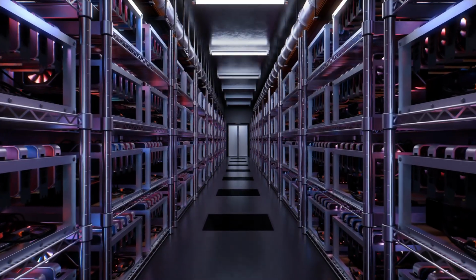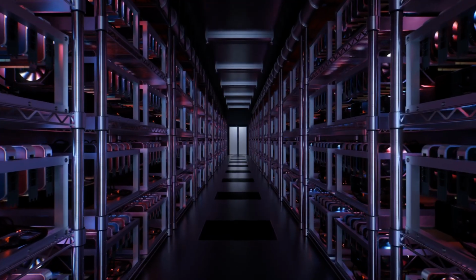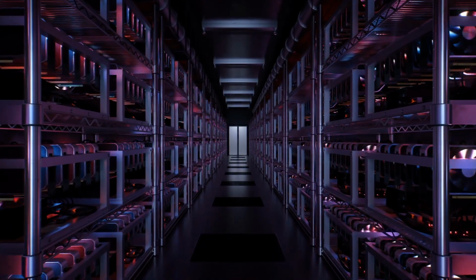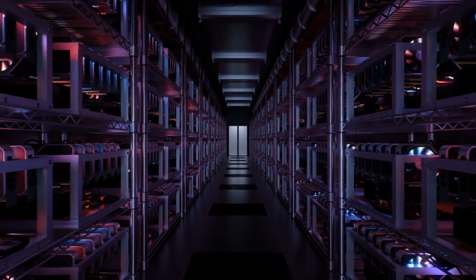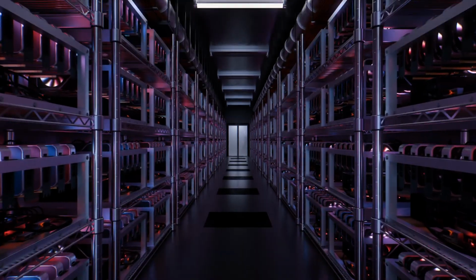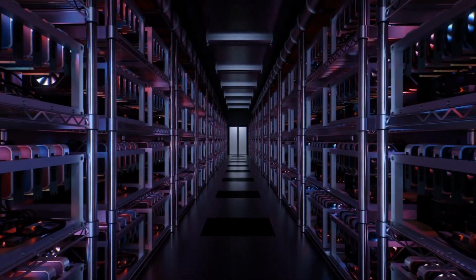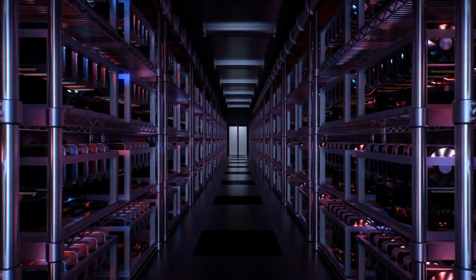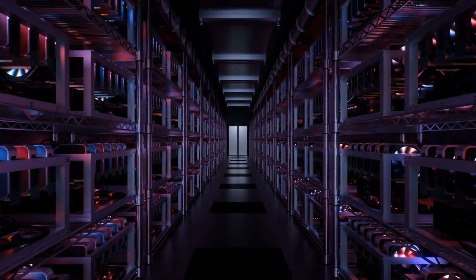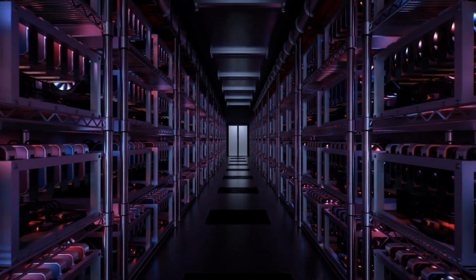So how does liquid cooling change the math in that denominator? By utilizing the physical properties of water as a transport mechanism instead of air, you drastically reduce the facility power required. We noted earlier that this Supermicro CDU only requires 18.5 kilowatts of electrical power to transport an entire megawatt of heat out of the system.